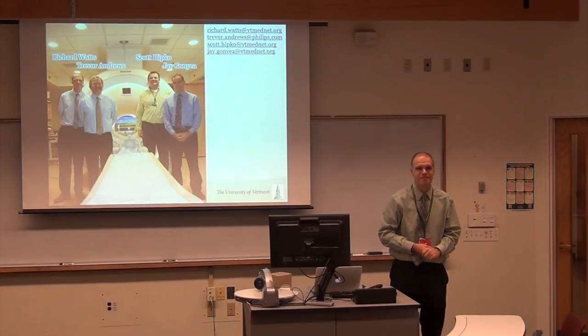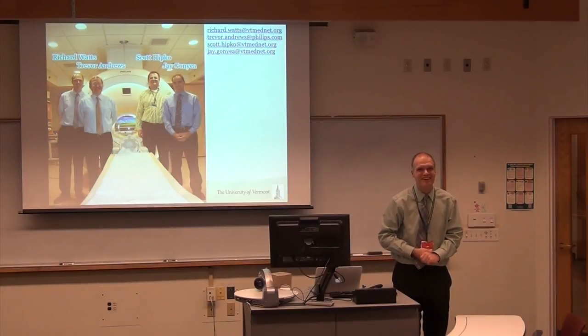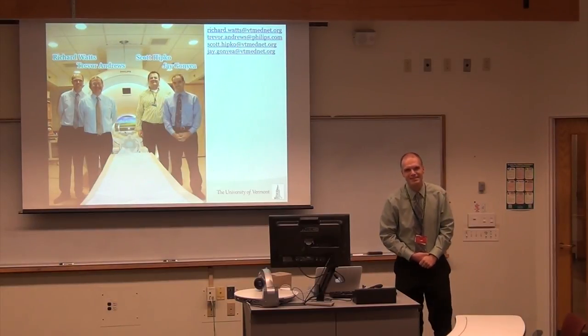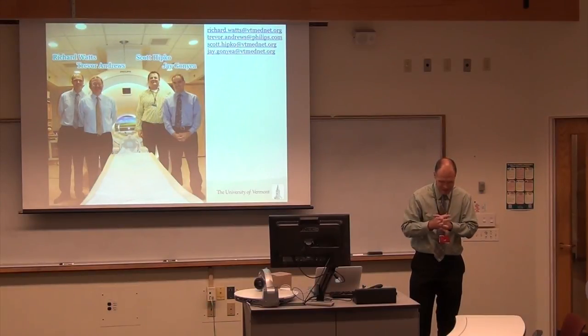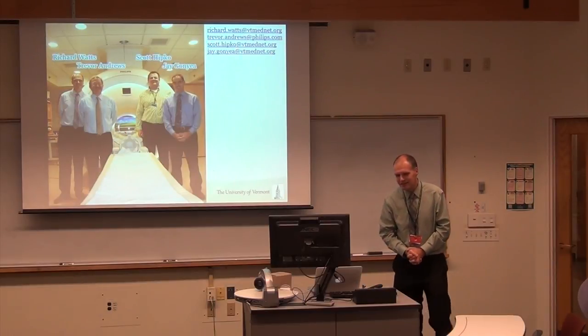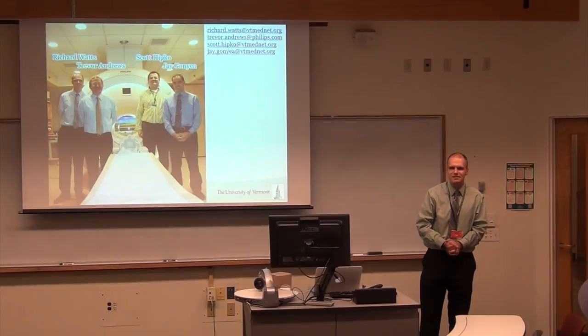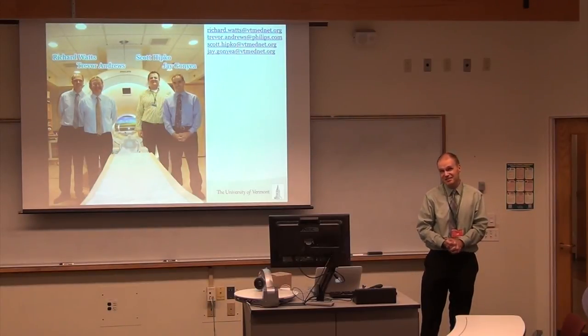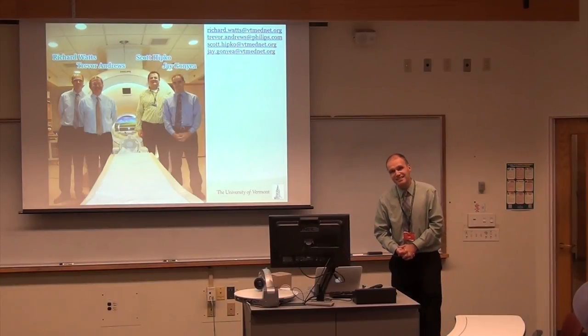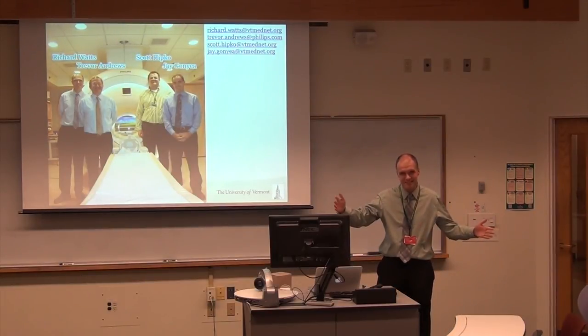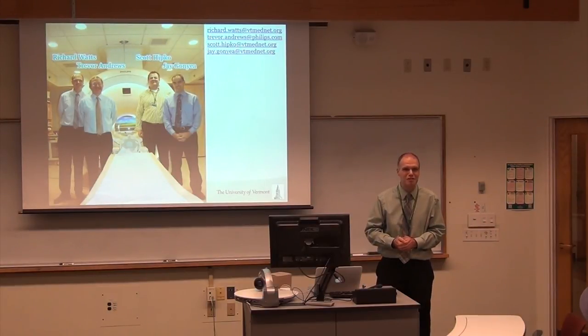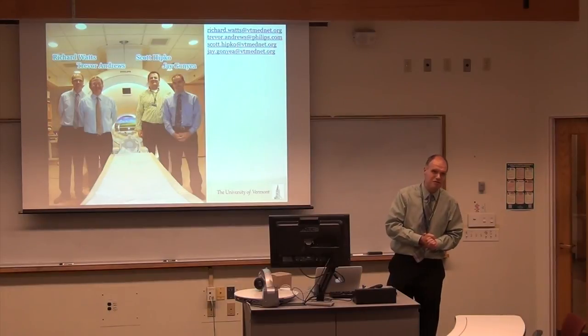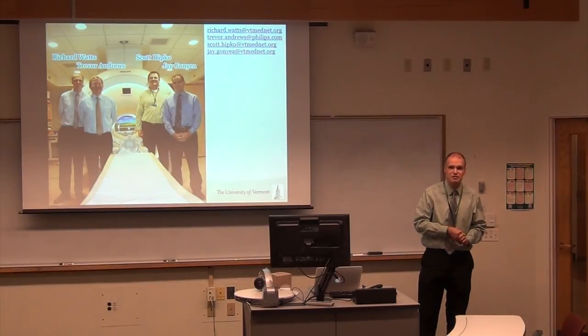Sorry, how about cost? That I don't know about, actually. There are advantages and disadvantages in what you can see and not see. If one costs 1,000 times more than the X-ray... Cost, okay. A 3 Tesla MRI machine costs about $3 million. A CT scanner might be $500,000 to $1 million. A PET scanner, $1 or $2 million. If you need a cyclotron, that's another few million dollars. It's in that sort of $500,000 to several million dollar range. A cheap MRI scanner might be $1 million, but actually the facility cost is quite high because you have to have a shielded room, so you're almost talking about the same amount for the facility as for the scanner itself.